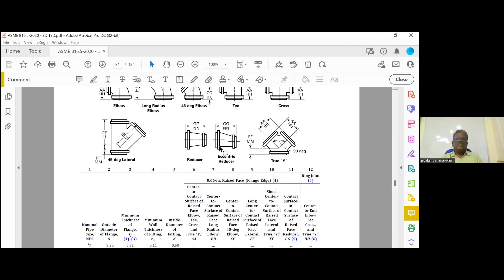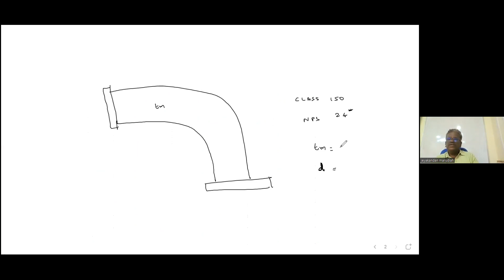So we have taken class 150. What is the NPS we have taken? NPS 24. So it is here. This is the minimum wall thickness TM. What is the TM for this fitting? 0.57. What is the diameter? This is outside diameter, not what we need. D, the inside diameter, is 23.25. So first we take from the table TM is equal to 0.57, and D is 23.25, all in inches.